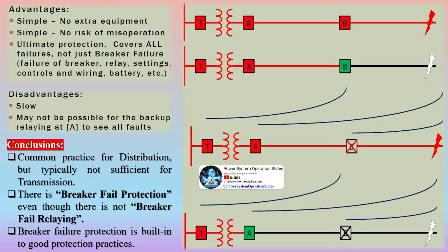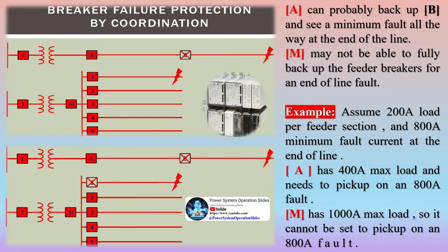Consider what happens when breaker failure protection itself malfunctions. This will result in isolation of healthy loops of the network, which is also not acceptable. Therefore, more care is needed when setting the breaker failure mechanism in the system. A relay engineer can judge that one reason for this malfunction is a shorter delay applied to all sorts of faults.